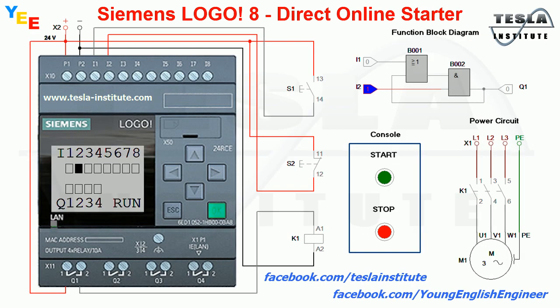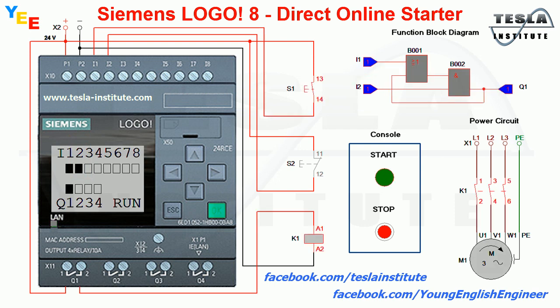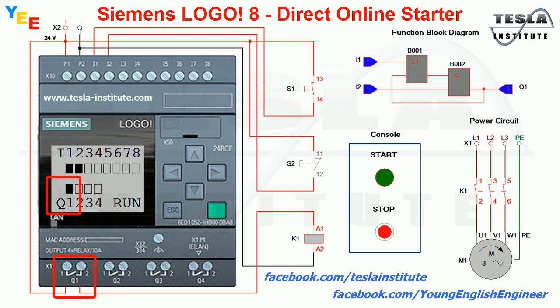Now let's see how it works in our DOL circuit. As push button S2 is normally closed, when it is not pressed it always gives a plus 24 volts on input I2. On the LCD display we see that input I2 is in a high state. The high state is also visible on input I2 of the function block diagram. Then when we press push button S1, plus 24 volts appears on input I1, and output Q1 goes to high state.